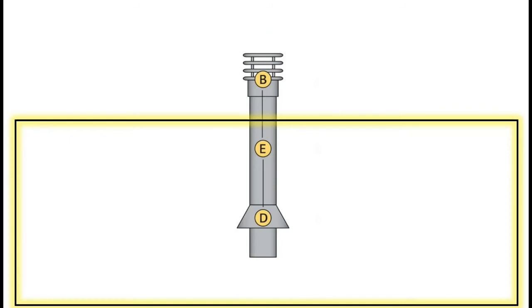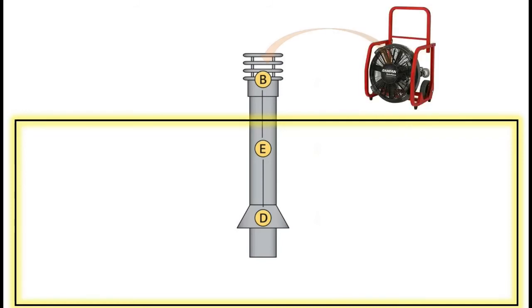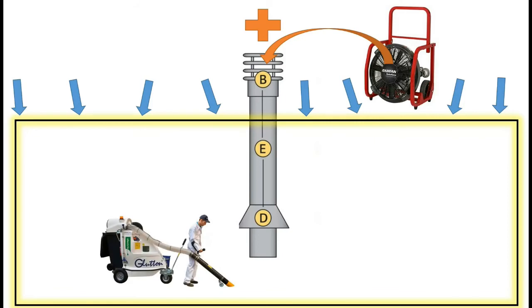However, if we have the same scenario, but I'll show you a position that you can get into where you have extra pressure outside and negative pressure inside, then you end up with positive pressure at the terminal and negative pressure at the base of the flue inside the room. This leads to flue reversal and products of combustion coming back into the room.